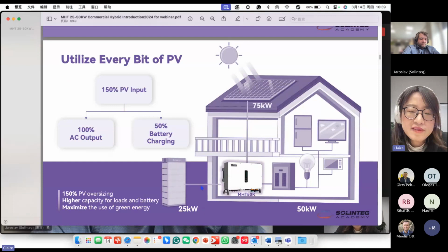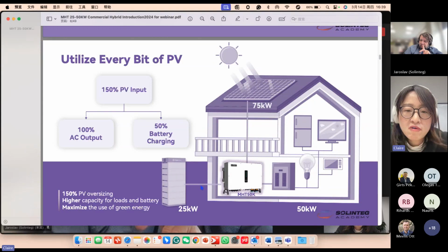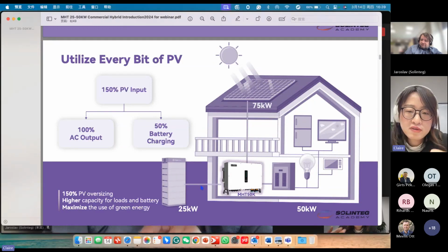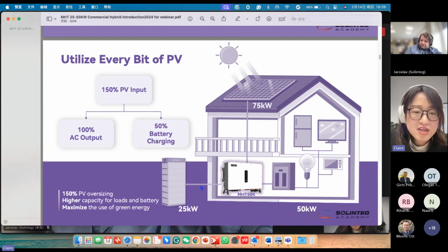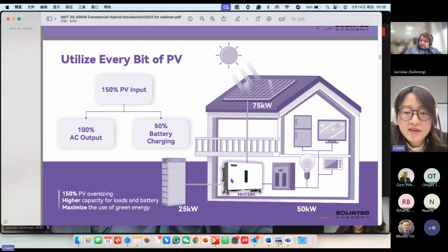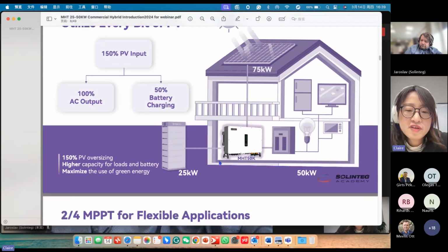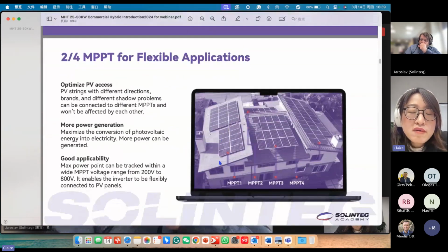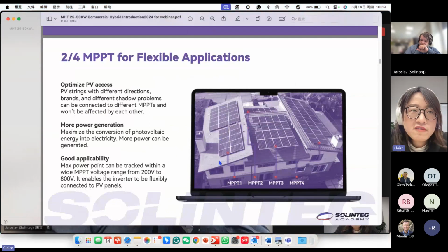And this slide shows the 150% PV oversizing, which can provide the customer more power to supply the loads and charge the battery at the same time. We can see this is a 50 kilowatt inverter. We can have 75 kilowatt panels on the top. So 50 can be used to supply the load, another 25 to charge the battery. So it's very efficient. And we also have 2 versions of the 25 to 50 kilowatt inverter.